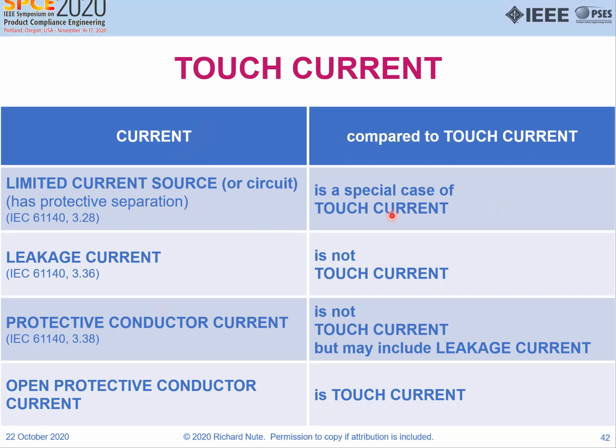However, if we're going to compare all of these things with touch current, which is a limited current source, it's a special case of touch current as protective separation. Leakage current is not touch current if we follow the definitions in 1140. Protective conductor current is not touch current, but may include leakage current. However, an open protective conductor is touch current.